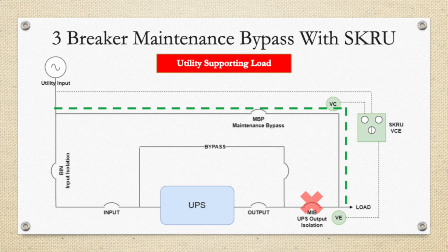So if your load is on maintenance bypass, you can't load test the UPS system because there will not be enough capacity from that feeder breaker. And number 2, even if you're on maintenance bypass and you attempt to restart this UPS, and if there's a fault in the UPS or some other fault occurs in the input or internal bypass circuit of the UPS, you could trip the single feeder breaker to the UPS. So a 3-breaker maintenance bypass, if you only have 1 breaker to feed the UPS, is certainly better than nothing, but it's not the ideal configuration.